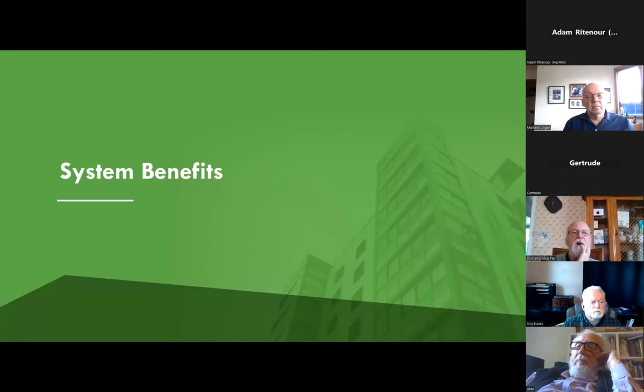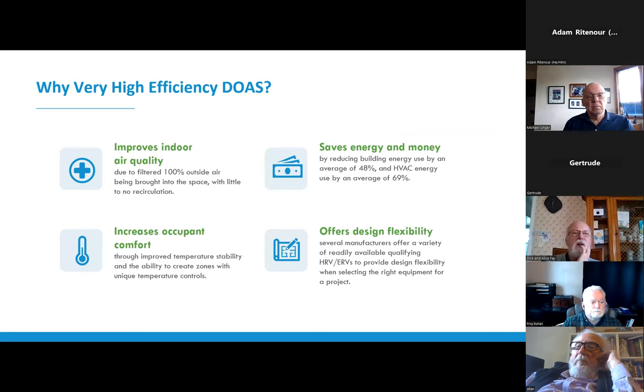So what are some of the system benefits of a VHE DOAS system? Why would we upgrade our HVAC if it isn't broken? Well, first of all, it improves indoor air quality by bringing in that 100% outside air with little to no recirculation. And that's a really big point for NEA to make. It saves energy and money. So high performance HVAC saves energy, which in turn saves money. And our field testing has shown that when we compare the existing HVAC systems to VHE DOAS, VHE DOAS saves on average 48% of total building energy and 69% of HVAC energy in Northwest commercial buildings.